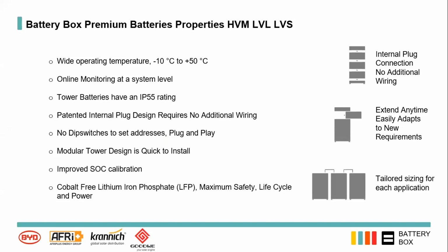The other great improvement is online monitoring at a system level. Previously, if you were a technician, you had to sort out a battery, you had to get your laptop, your cable, go to site and plug it in, download logs. Now the batteries can be monitored online at a system level, so you can see the cell voltages, errors, etc. The tower batteries have got an IP55 rating. That allows a lot of flexibility in terms of where they can be installed. We're going to touch on that a bit later.